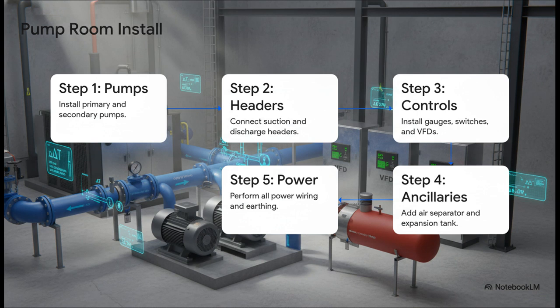But step 3 is where the magic is. See those gray boxes, the VFDs? Those are variable frequency drives. They're like a super smart gas pedal for the pumps, adjusting their speed in real time to match exactly what the building needs. It saves an unbelievable amount of energy. Steps 4 and 5 are just adding the essential safety gear and, of course, the power to make it all go. And just like that, the system has its heartbeat.